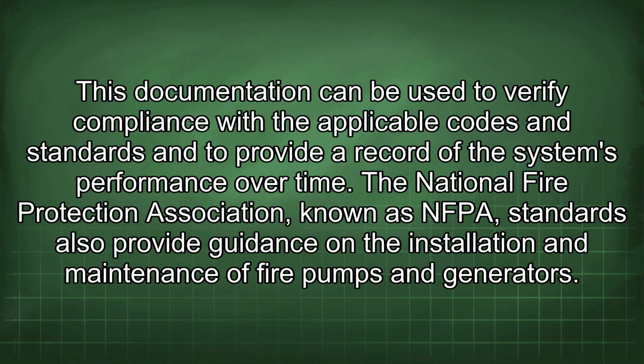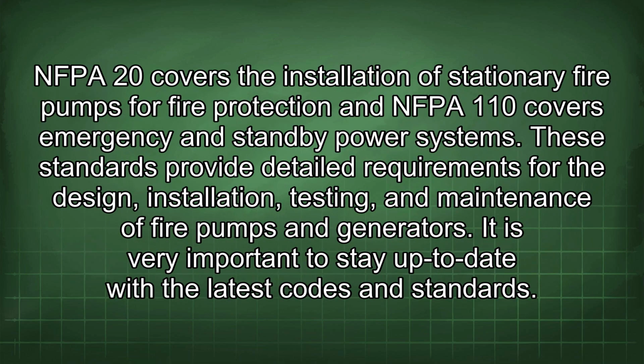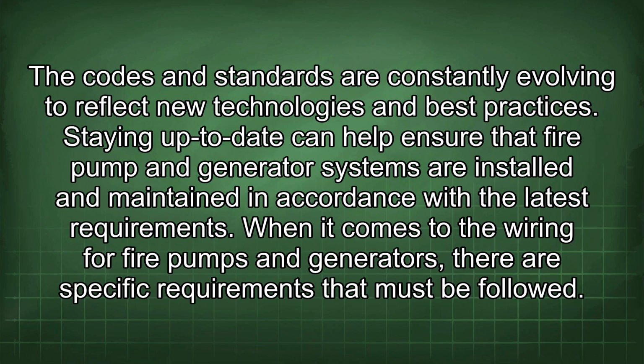The National Fire Protection Association, known as NFPA, standards also provide guidance on the installation and maintenance of fire pumps and generators. NFPA 20 covers the installation of stationary fire pumps for fire protection, and NFPA 110 covers emergency and standby power systems. These standards provide detailed requirements for the design, installation, testing, and maintenance of fire pumps and generators. It is very important to stay up to date with the latest codes and standards. The codes and standards are constantly evolving to reflect new technologies and best practices. Staying up to date can help ensure that fire pump and generator systems are installed and maintained in accordance with the latest requirements.